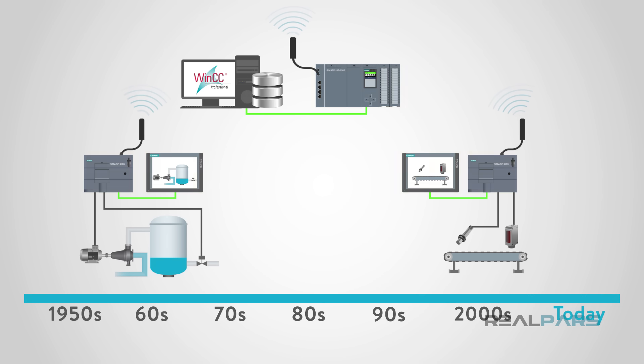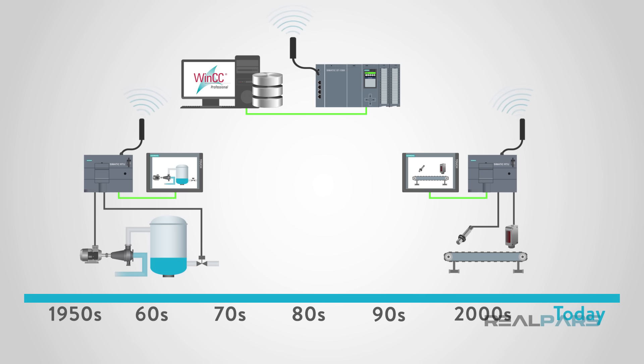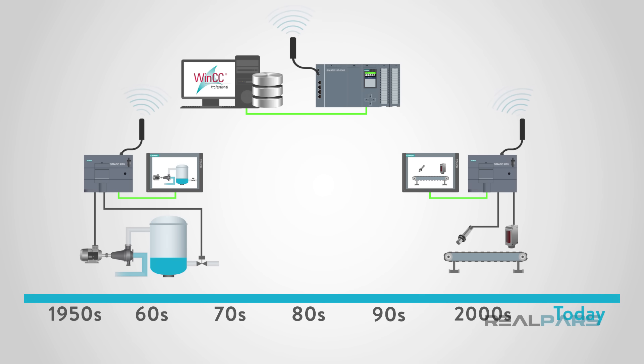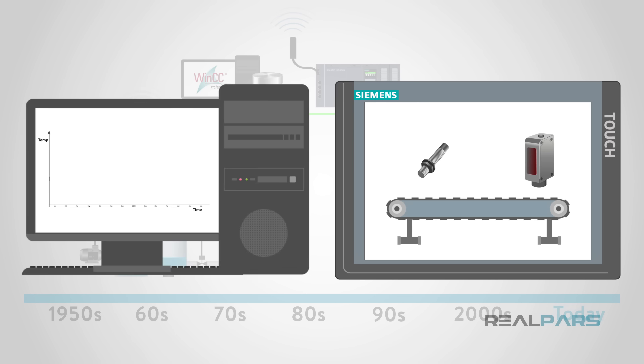Essentially, SCADA is a collection of hardware and software components. This collection begins with real-time data collected from plant floor devices such as pumps, valves, and transmitters. These components don't have to be from a particular vendor — they just need to have a communication protocol that the processor can utilize. Data collected from the field devices is then passed to the processors such as PLCs. From the processor, the data is distributed to a system of network devices, which may be HMIs, end-user computers, and servers. On the HMI and end-user computer, graphical representations of the operations exist for operator interactions such as running pumps and opening valves. This data may also be analyzed and used to enhance plant production and troubleshoot problems.